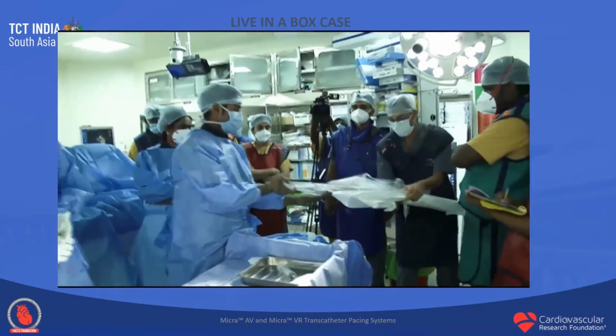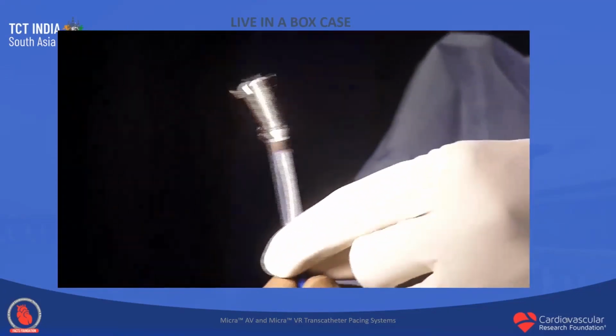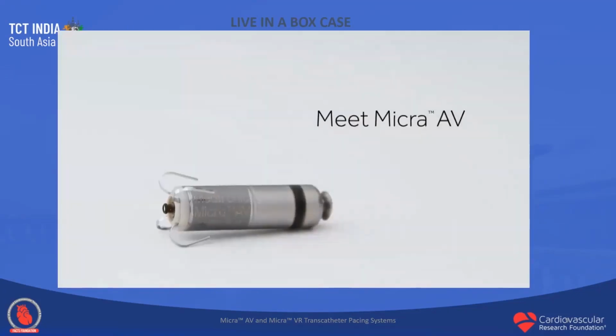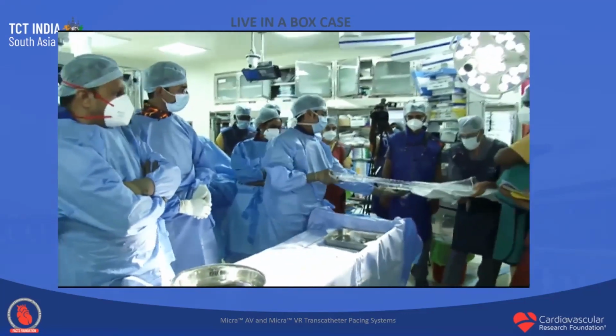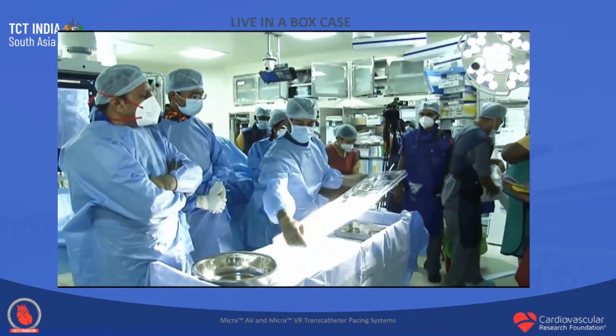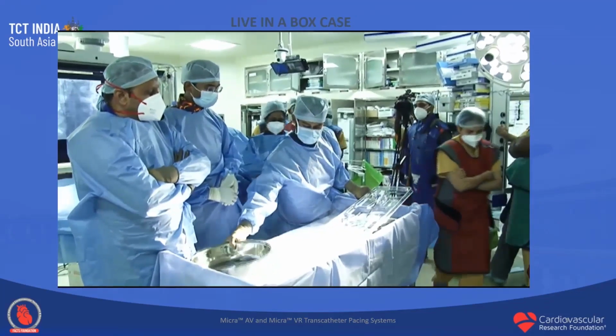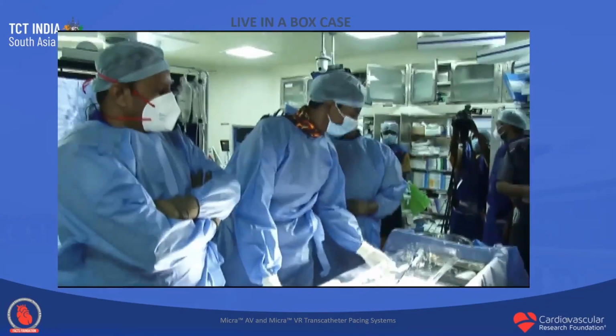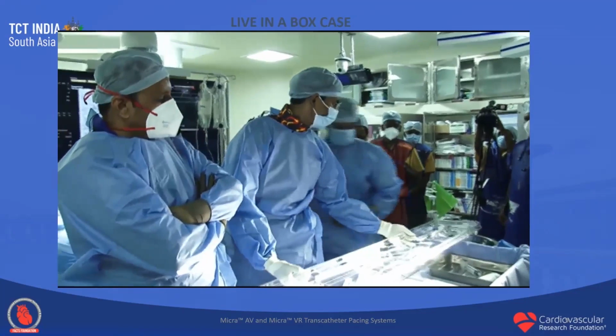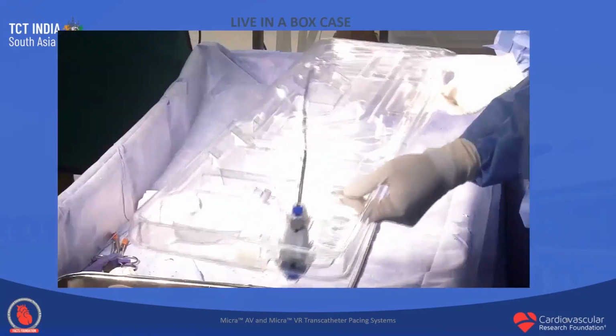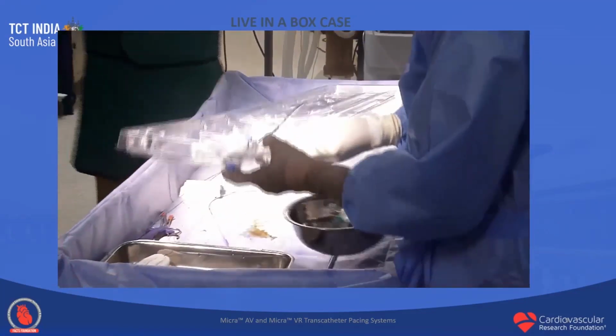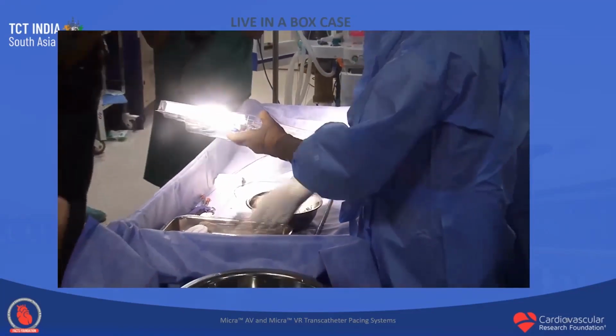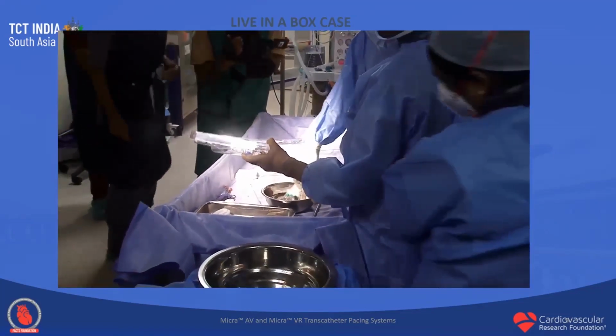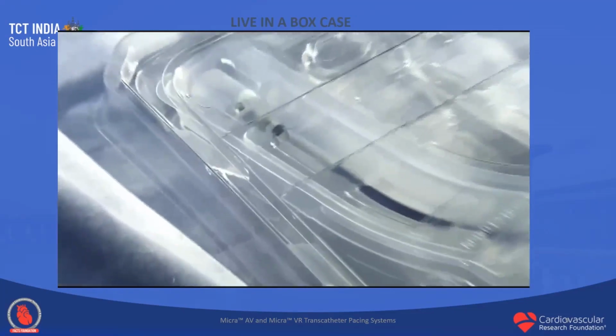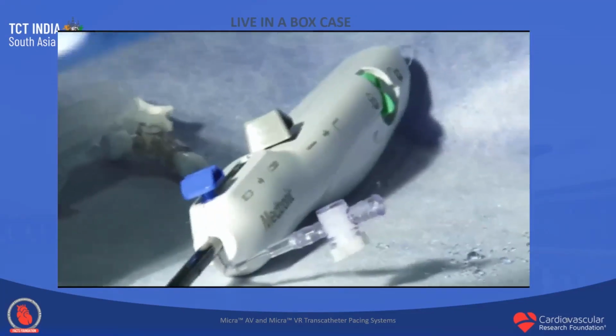Now you have got two types of leadless pacemaker. One is the VR, a single chamber one, and the AV is a dual chamber one. The sensing of the atrial activity is completely different to the normal pacemaker sensing. In a normal pacemaker, you have a lead which senses, and accordingly the ventricular lead paces. Here the sensing is done by a special sensor which is at the end of the leadless pacemaker. So it senses the atrial activity, and according to the atrial activity it will coordinate and pace the ventricle.